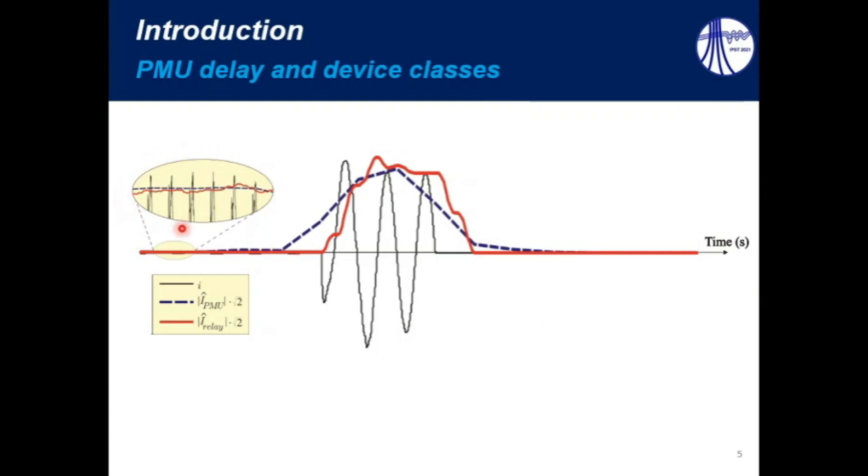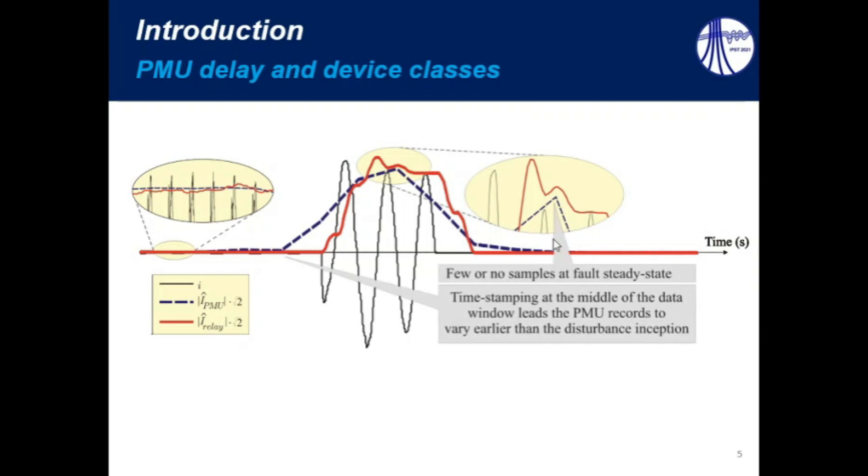we can see that the phasor estimation estimated by the PMU is more stable, but when we consider the fault period, we can see that the relay algorithm allows you to have more samples during the fault period, whereas the PMU estimation only reaches the steady state fault period here, and then it goes to the third period, which would be like a post-fault period. So, we can see that fewer samples can take place at the fault steady state, if we consider the PMU estimation, and we can see also that the timestamps are used at the middle of the data window, leading the PMU records to vary earlier than the disturbance inception.